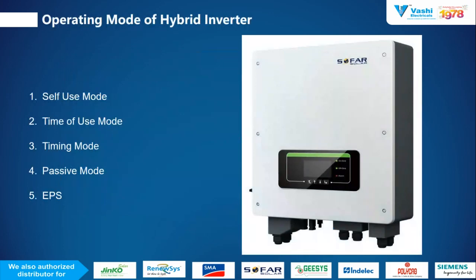Now we will see the different operating modes of the hybrid inverter. These are the 5 modes of the hybrid inverter. First is self-use mode, second is time of use mode, third is timing mode, fourth is passive mode, and fifth is EPS mode. So these are the 5 basic operating modes of the hybrid inverter. They will give you a briefing on when the inverter is working on grid, when it is working off grid, and when it is working in EPS mode. Next.